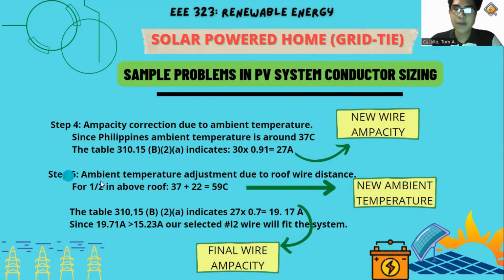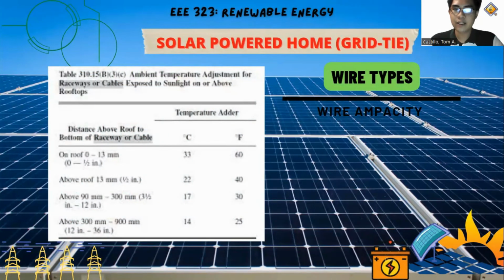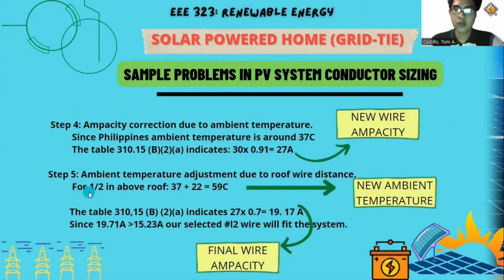So, step 5, ambient temperature adjustment due to roof wire distance. So, hindi naman natin ilalagay yung solar panel natin sa loob, kundi sa may bubong. Dahil mas mataas yung temperature sa bubong, kaya magkakaroon tayo ng new ambient temperature. So, yung solar panel natin is ilalagay natin sa above the roof. Kaya yung temperature adder natin is 22 degrees Celsius. So, 1/2 inch above the roof. So, yung 37 degrees Celsius na ambient temperature natin, ipa-plus natin yung temperature adder natin na 22 degrees Celsius. So, magiging new ambient temperature natin is 59 degrees Celsius.